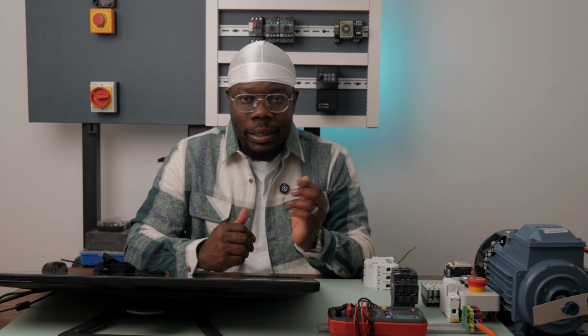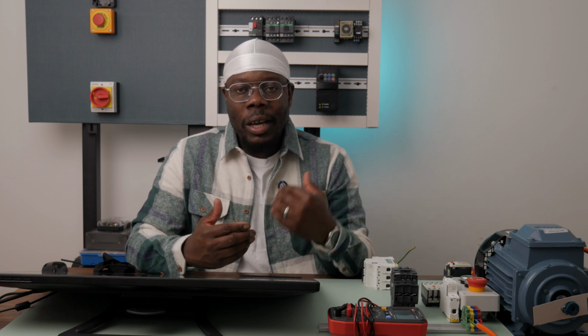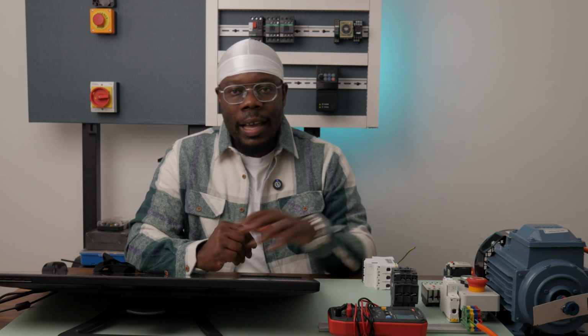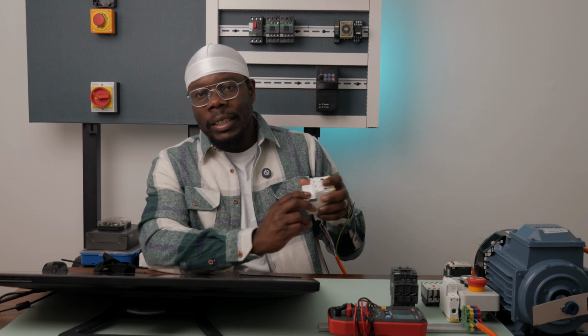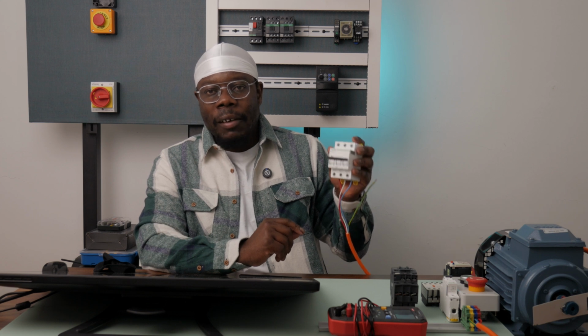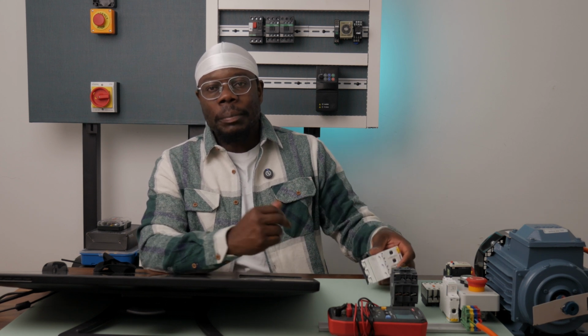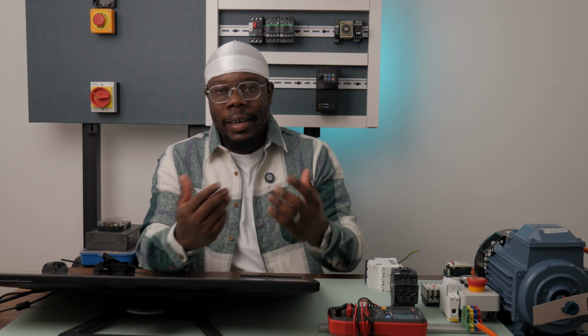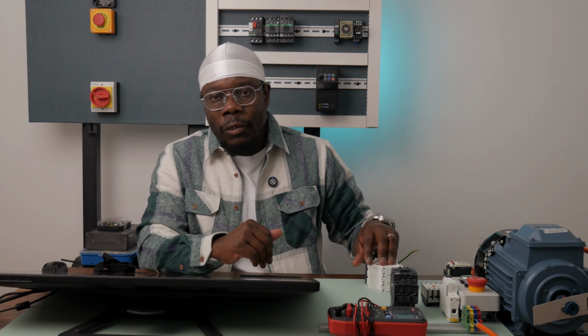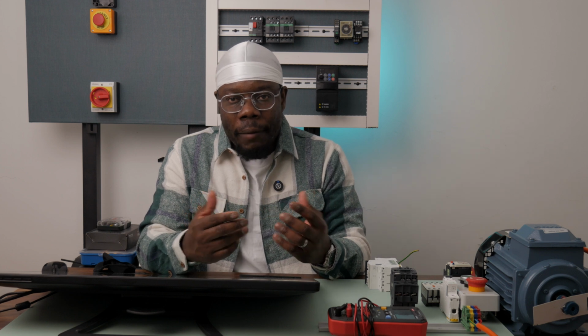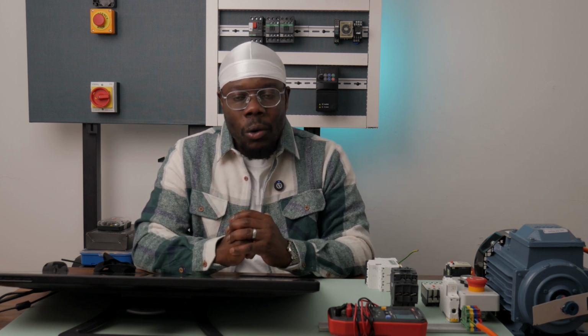I know that even though some of you might not have experience with electric motor controls, you can almost tell that this is not quite a good idea, due to the reason that you are exposing yourself to high switching currents when you're using your circuit breaker as a switch, because this circuit breaker is not designed for starting and stopping electric motors. So you're exposing yourself to high switching currents and an arc that could cause damage to the circuit breaker itself, or even pose the risk of a fire. So that's the reason why you need an external circuit for starting and stopping an electric motor. And this external circuit is what we call the control circuit.